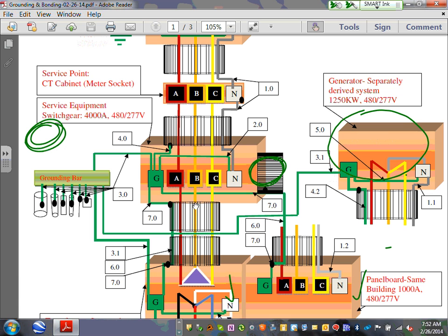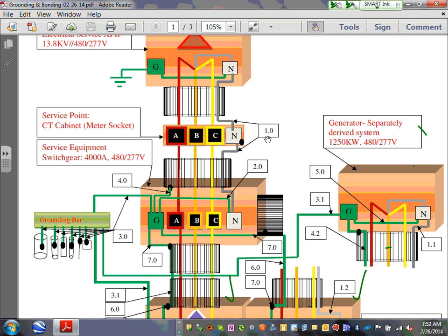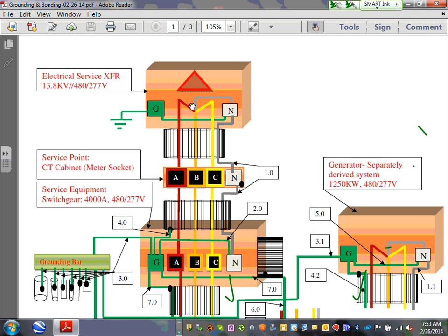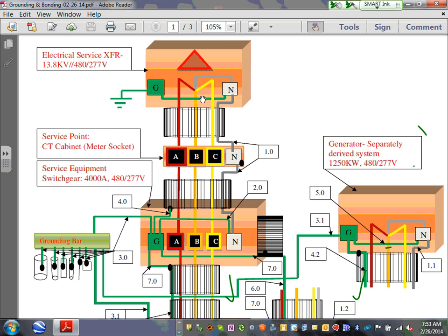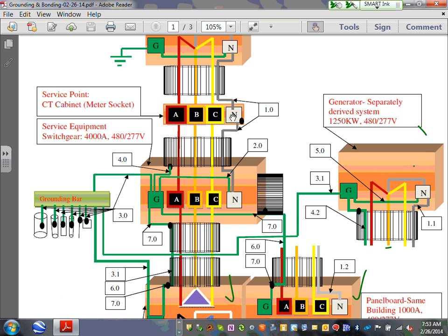So let's go. I'm going to walk you guys through the whole system, and then we'll go size it. I have an exercise on that one. So let's talk about the first, number 1. Let's start with number 1. So Adam, number 1 is 1.0. This is called the grounded conductor. That's the neutral that comes out of the Y. Can you guys see that gray? It comes out of the Y of the utility transformer and ties to the CT cabinet neutral.